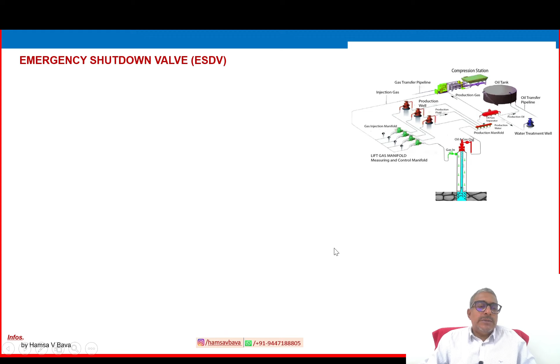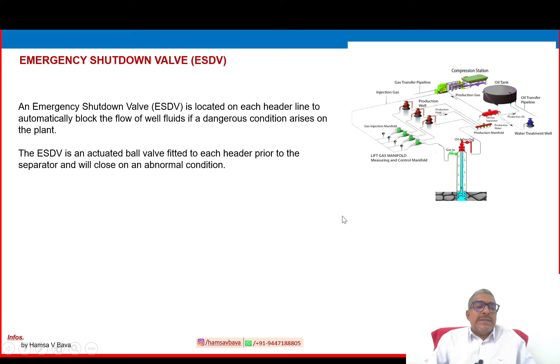Another one is the ESD, emergency shutdown valve. For every manifold, before the production system, we keep an ESD to shut the well or the manifold and protect the downstream area and the manifold itself from abnormal situations like a fire or gas leak, any high pressure or low pressure, instrument system failure, or various emergencies. An emergency shutdown valve, ESDV, is located on each header line to automatically block the flow of well fluid if a dangerous condition arises on the plant. The ESDV is an actuated ball valve fitted to each header prior to the separator and will close on abnormal conditions.